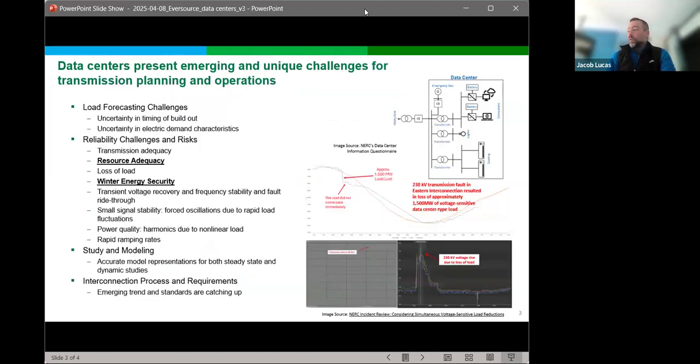And so I'll just touch on a couple things that Eversource is working on now, because we're trying to stay out ahead of this wave that we see coming. And these are not meant to be barriers. It's not what I'm saying, but we are trying to learn from other areas of the country. Hey, what are you all seeing? What can we do proactively to help facilitate the interconnection of these facilities? And so, yes, the long-term electric load forecast process that we have today, both at the Independent System Operator of New England, so the regional ISO's perspective, as well as our own local transmission owner load forecasts, we do not currently include large step loads like hyperscale data centers. This is absolutely something that is on our radar, and there are various key initiatives going on right now to figure out how to go about pulling that into our load forecasts.